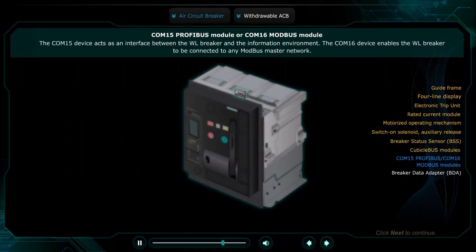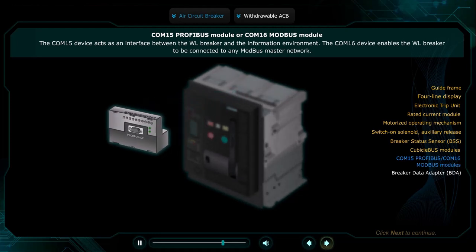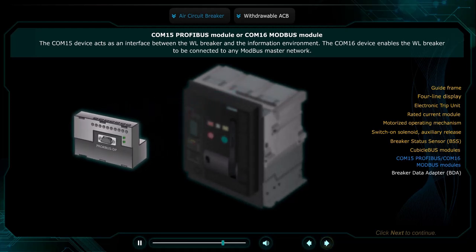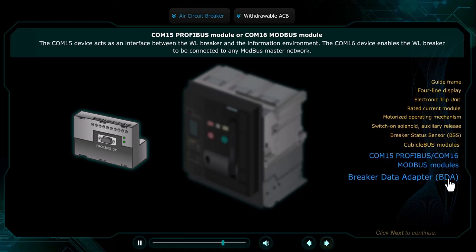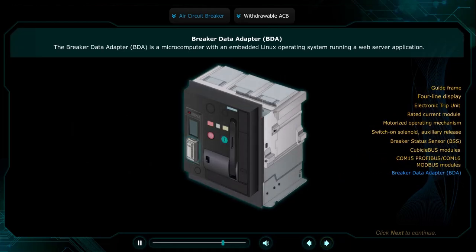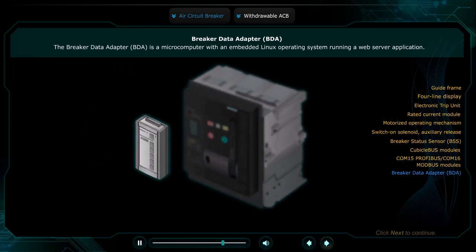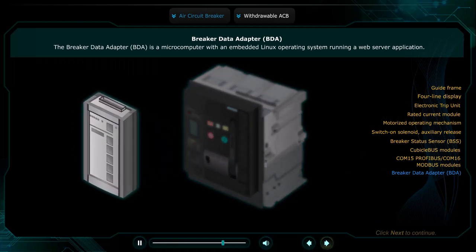The COM15 device acts as an interface between the WL breaker and the information environment. The COM16 device enables the WL breaker to be connected to any Modbus master network. The breaker data adapter or BDA is a microcomputer with an embedded Linux operating system running a web server application.